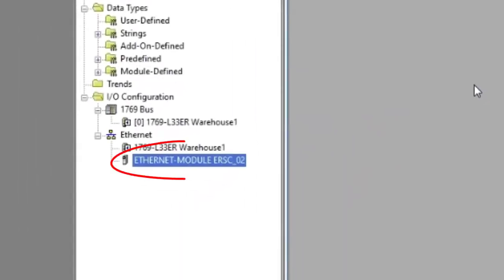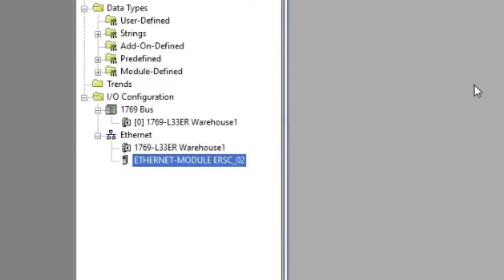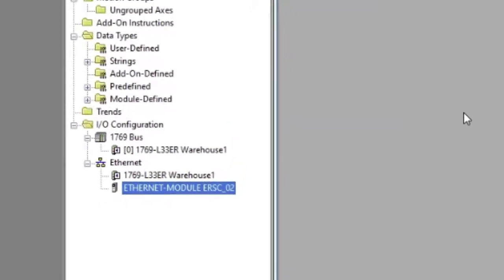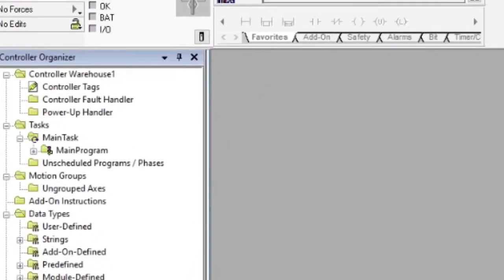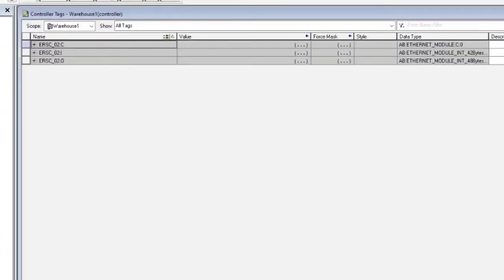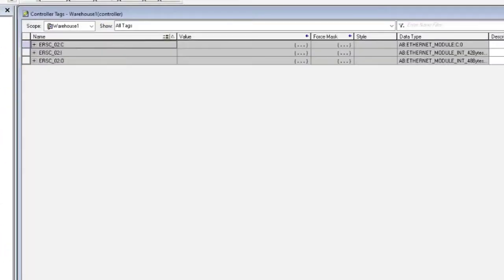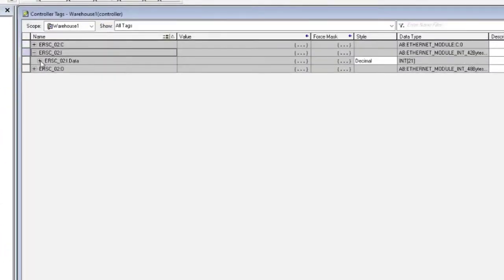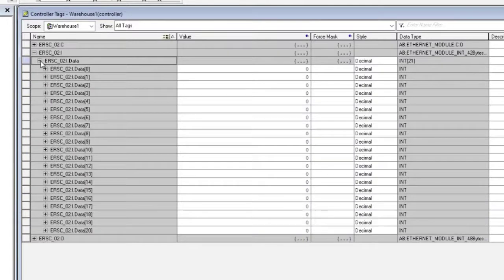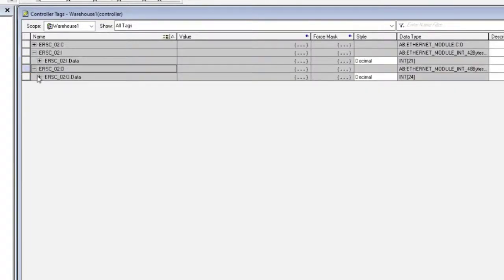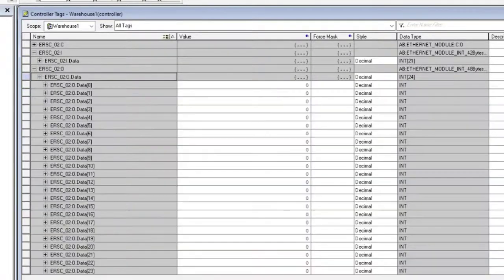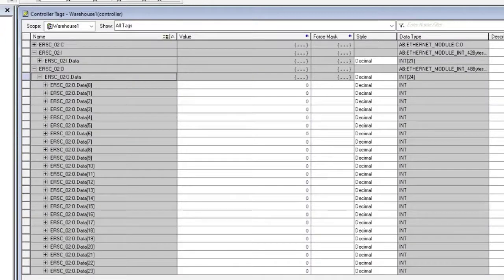Check your Ethernet tree to make sure the name of the module appears. Just for fun, let's check the controller tags to make sure the module was created correctly. There should be an integer array of 21 registers for the inputs and an integer array of 24 registers for the outputs.